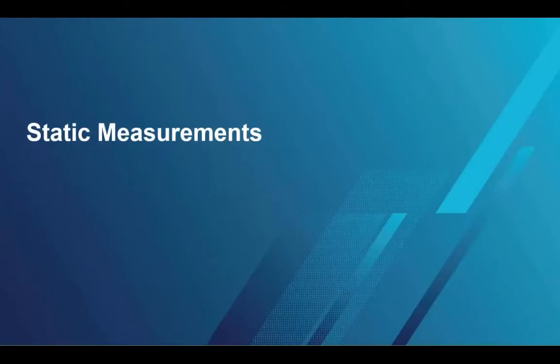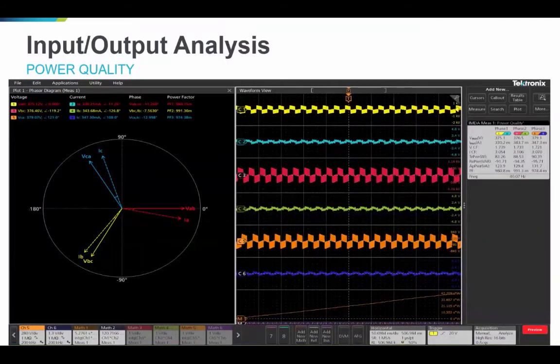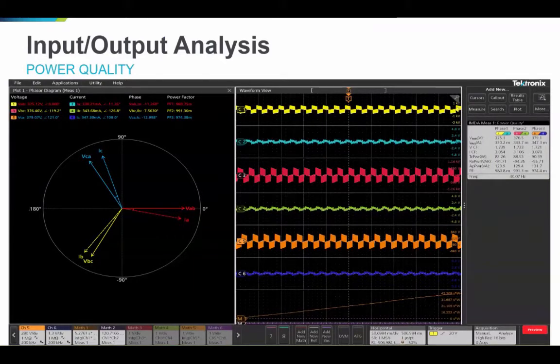For static measurements, you have input or output analysis for power quality. You capture your three-phase voltages and currents on the scope, set up the software, and you can measure RMS voltage and currents, crest factors, all the powers, power factor, and more. On the right-hand side you can see all the waveforms and associated math waveforms. On the left-hand side there is a phasor diagram associated with your voltage capture showing all the different angles between the voltages, currents, and between the phases.